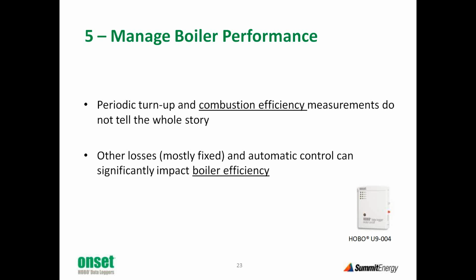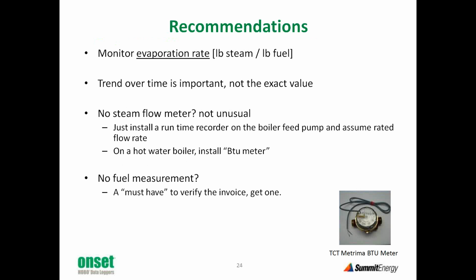For a boiler, the biggest losses aside from combustion are going to be radiation losses. It's a large, hot piece of metal that's radiating heat to the environment. And that's a fixed loss. In other words, since the boiler temperatures and pressures are about the same, no matter what the boiler load, you're going to lose that amount of heat no matter what the boiler load is. So if you've got a strip of paper that says your efficiency is 80-something%, be careful. That's not the whole story. And if you're running that boiler at partial load, your efficiency is probably a lot lower than you think it is.